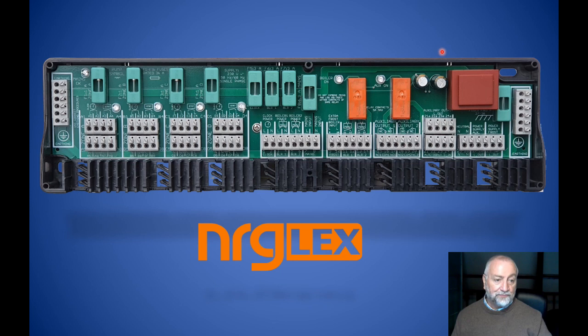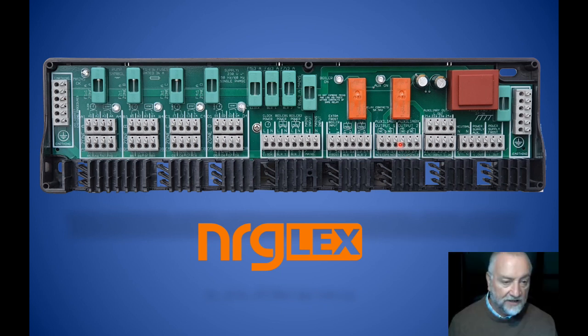Completely separately over here we have an auxiliary relay, and we have auxiliary inputs. We also have auxiliary power supply, all fed from a separate 3 amp fuse as well. If I put power into any one of those 4 auxiliary inputs, which are in series with connections directly above, so if this is connected to that, that's connected to that, and so on, and that's connected to that and that. So if I put power in here, any one of the 4 inputs will not backfeed with any other, but will close this relay. If that relay closes, the common will join from the normally closed to normally open here, and from the normally closed to normally open here. So now I can use that for additional zones, additional boilers, for auxiliary functions like hot water priority. It's way too much to talk about in this, but I'm just introducing it.